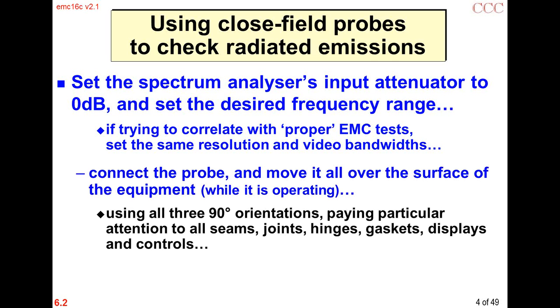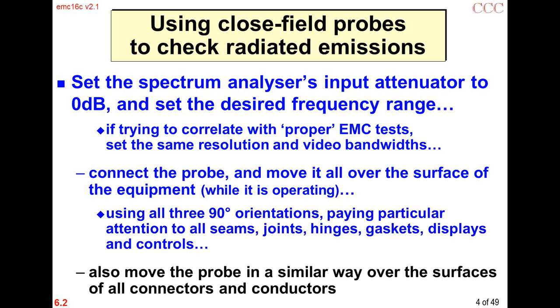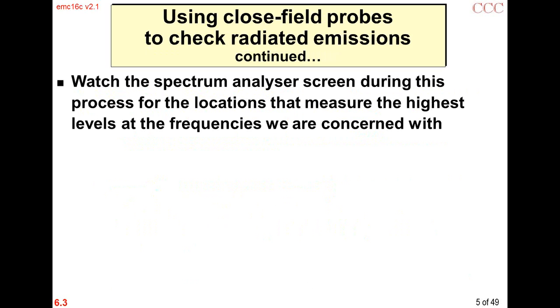If it's a magnetic field probe, then we need to use all 3 90-degree orientations, paying particular attention to seams, joints, hinges, gaskets, displays, controls, basically all the points where we tend to get leakages. And do the same thing on the surfaces of connectors and conductors. Ideally, you would see nothing. You just see the noise. If you see the noise, then you've got a good design. I mean the noise floor, that is, of the analyzer.